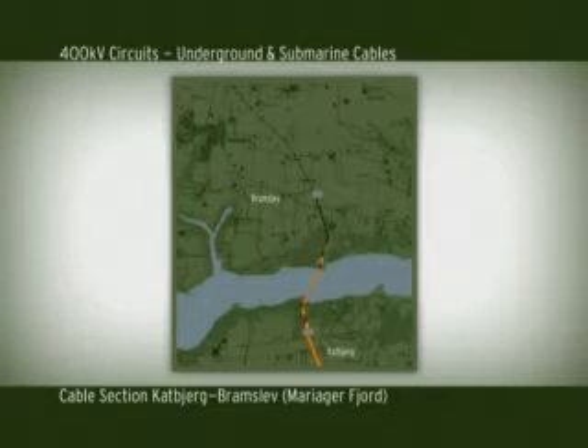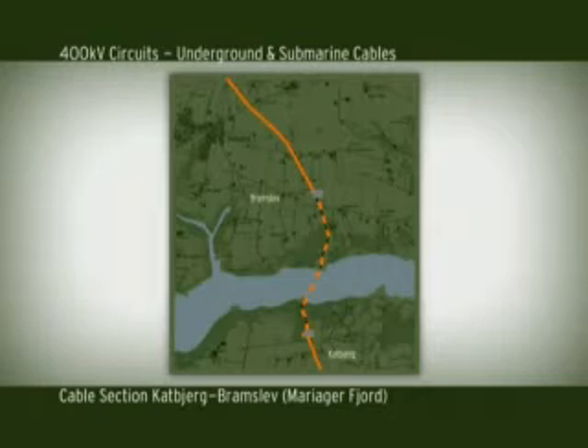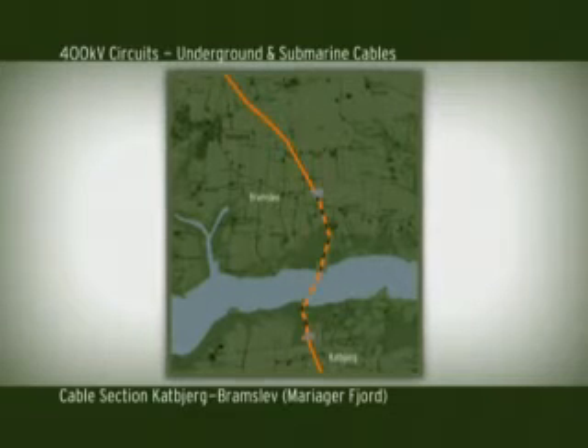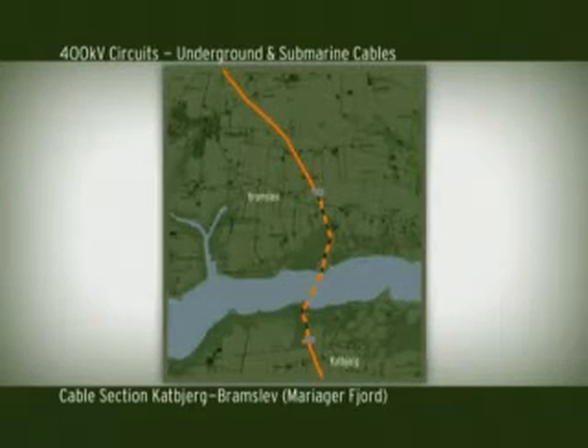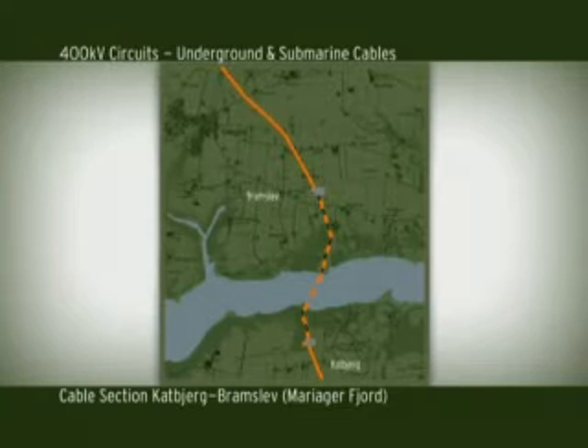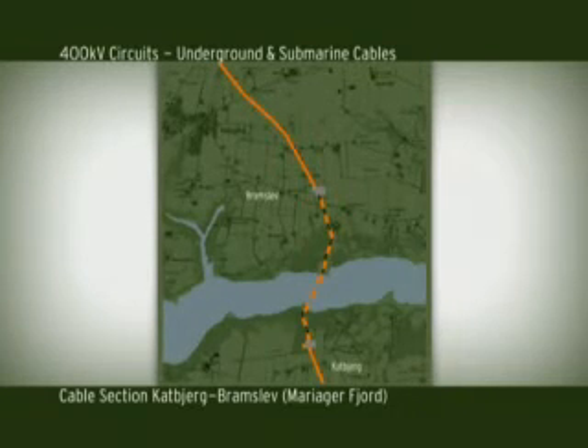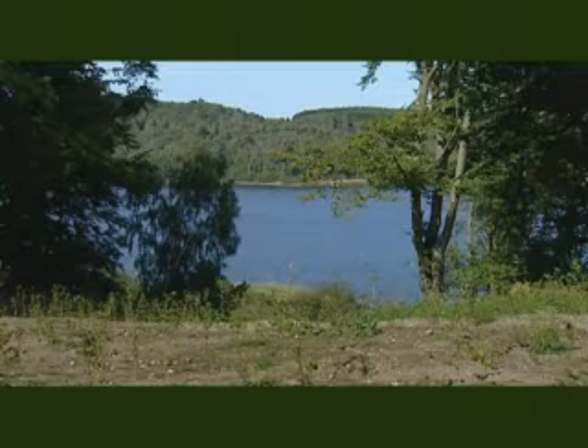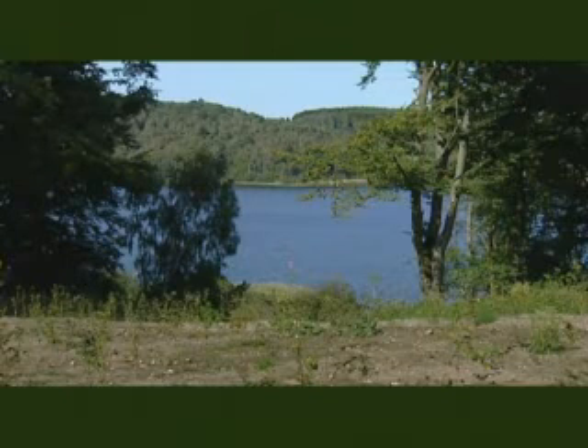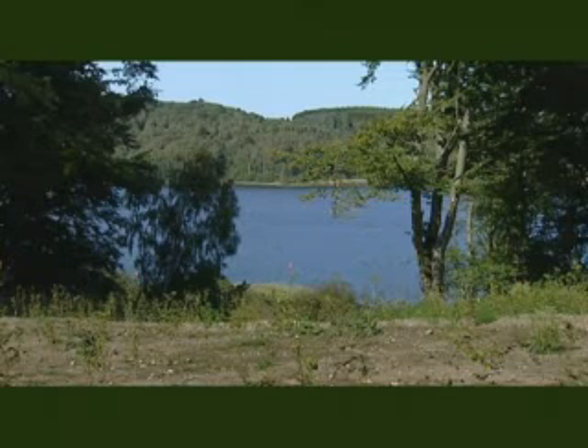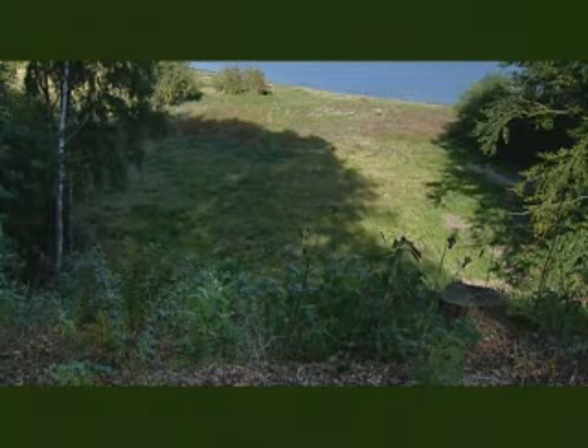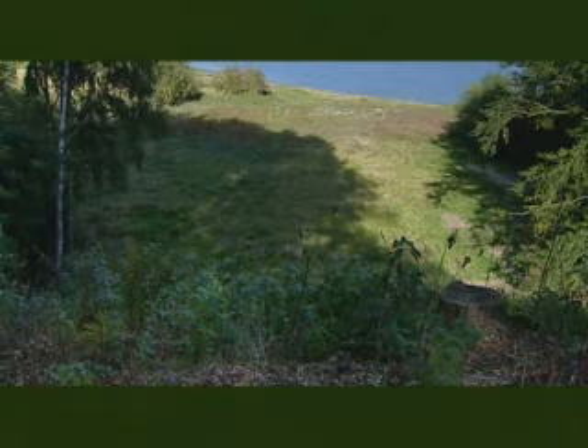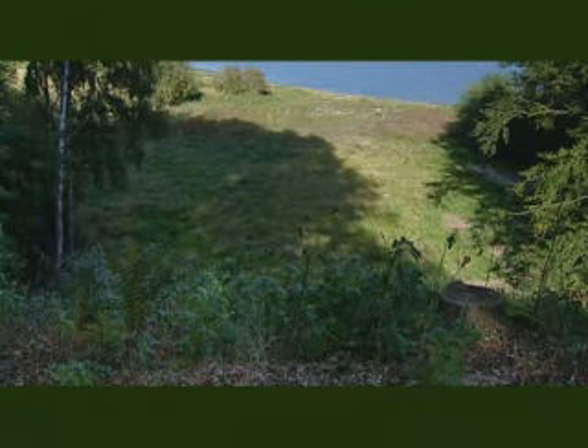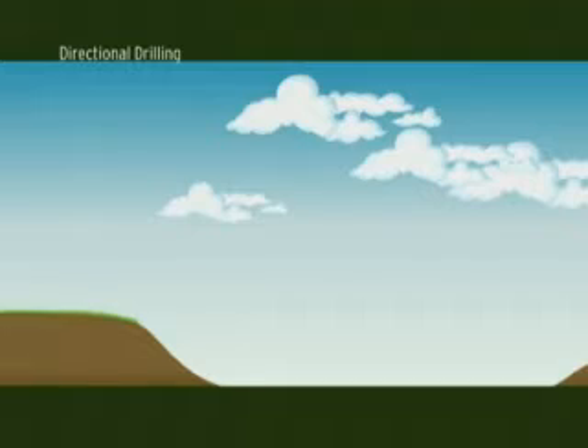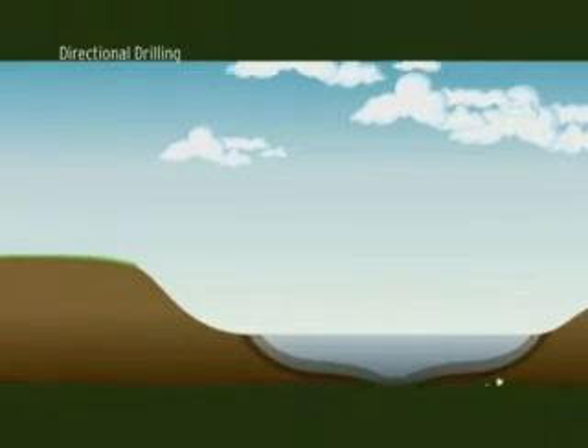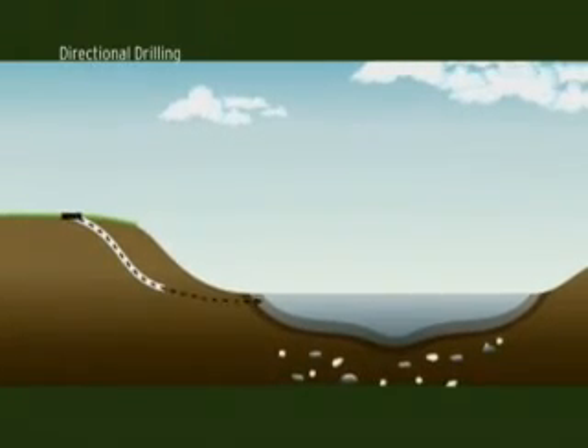Compound Katbjerg lies south of Mariager Fjord between Hobro and Mariager. Bramslev is on the northern side of the inlet. The section between Katbjerg and Bramslev is 2.5 kilometres long. The cables lie in agricultural land from Katbjerg to a point immediately south of the inlet. The banks down to the shore of the inlet are very steep. It was therefore not possible to lay the cables in an open trench. Instead, directional drillings were made and the cables pulled in pipes down to the shore.